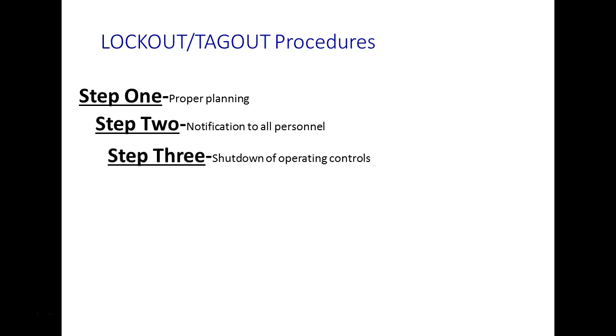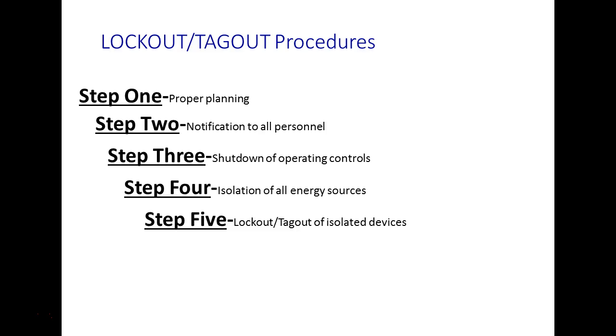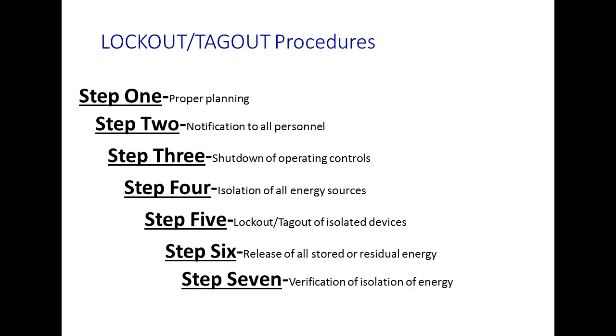Step 1, proper planning. Step 2, notification to all personnel. Then shutting down and operating controls, isolation of all energy sources, lockout tagout of isolated devices, release of all stored and residual energy, and verification of isolation of energy. And that's what you brought up a while ago, Dwayne. We don't just lock it out, we verify that the energy level is gone, right? A lot of your pneumatic systems and pressure systems have pressure gauges, so when you disconnect it, you can verify with the gauge that the pressure is gone. All right, you understand? And then, of course, there's only one real way to verify that the power is off the machine, instead of trying to operate it. And that's not a good idea either, right?